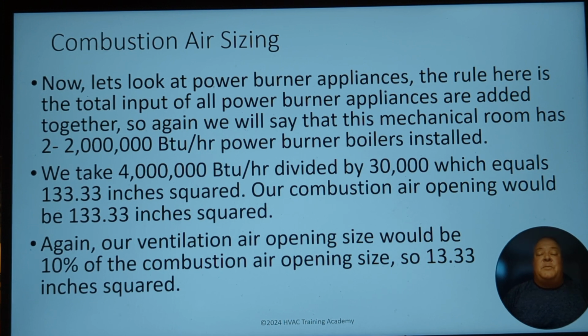The big thing to keep in mind is that the ventilation air opening size can never go less than 10 square inches. There's a trick question a lot of times on the test that indicates a number lower than 10, because your combustion air opening size is, let's say, 70 inches. So of course 10% of that would be 7 inches. You have to keep in mind that the minimum opening size for your ventilation air is going to be 10 inches. That's in the code.